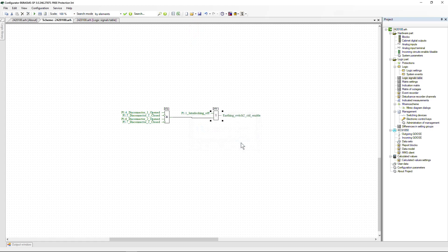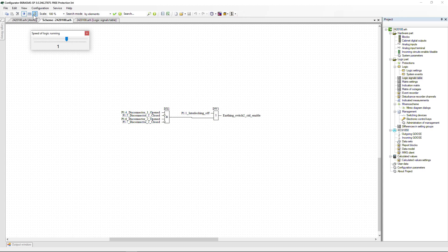Adjustment of the created logic can be done in two ways. The first is to start simulation mode in the configurator software and simulate the operation of inputs by clicking on the necessary signals in the logic diagram. Signals displayed in red indicate a state corresponding to logical one; signals in black indicate logical zero. When all conditions are met for enabling control of the switching device, the signal at the output of the logic element will be displayed in red. If it is not, check the correctness of compilation of the interlocking logic or the correctness of the conditions.